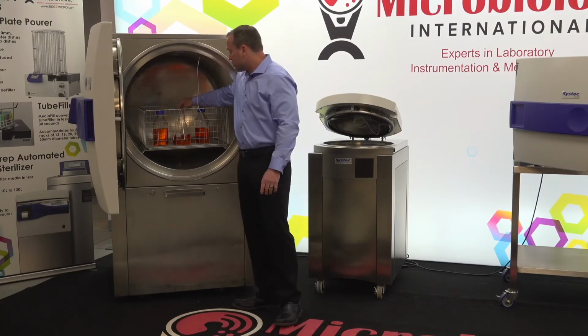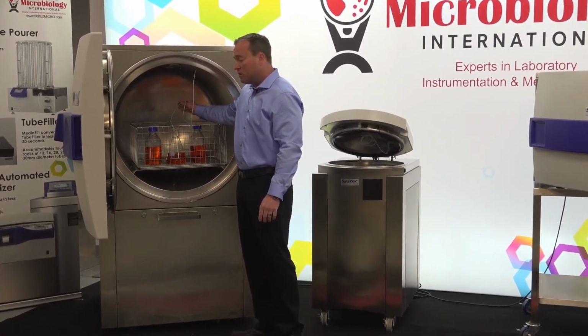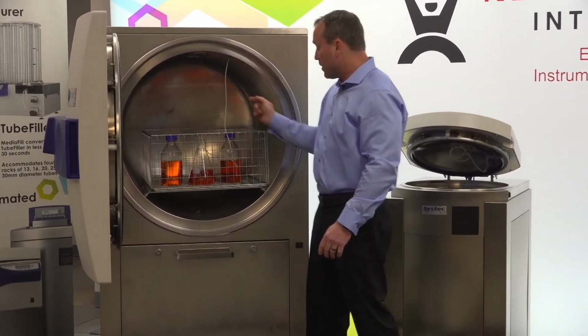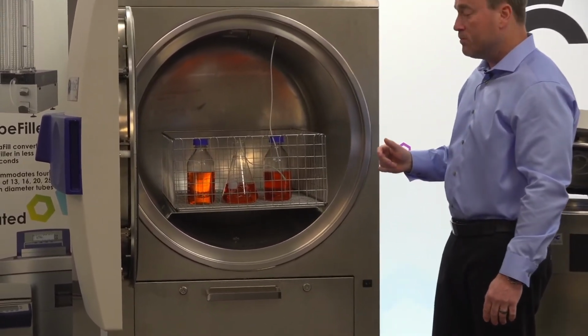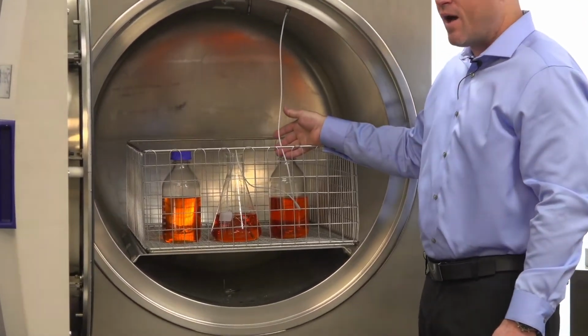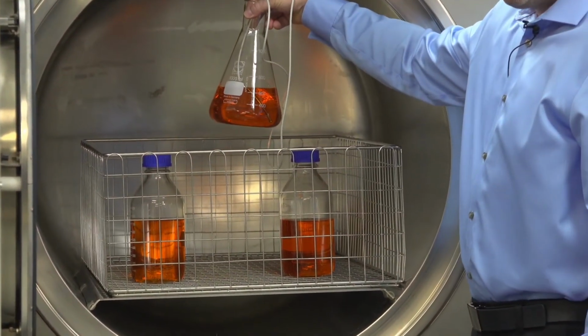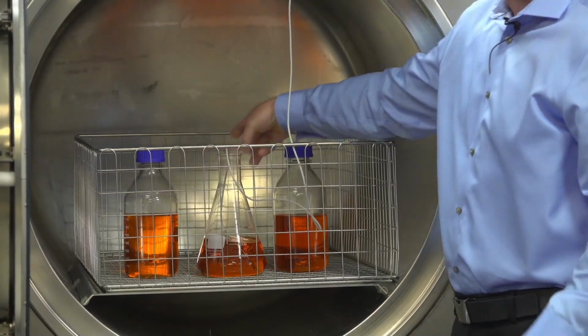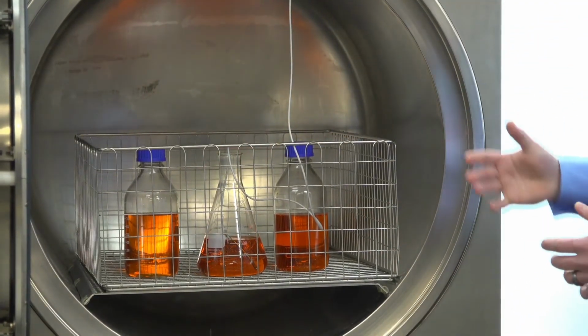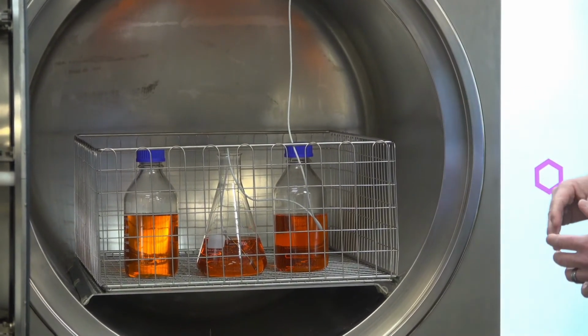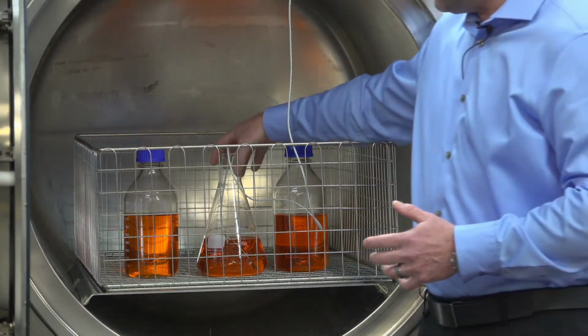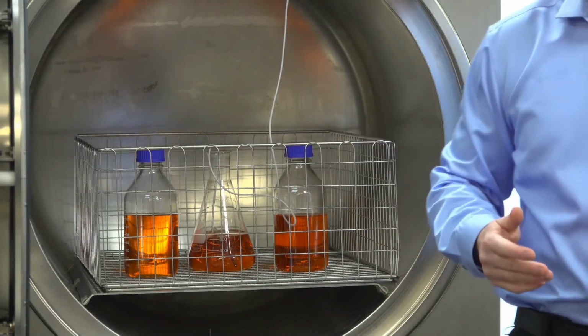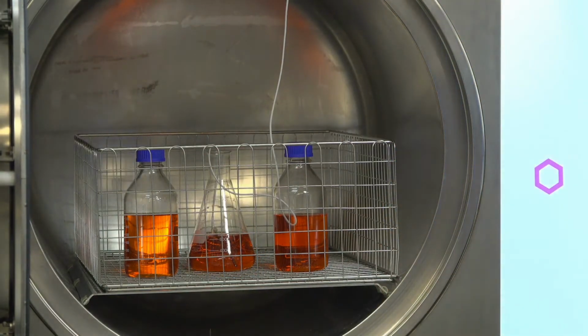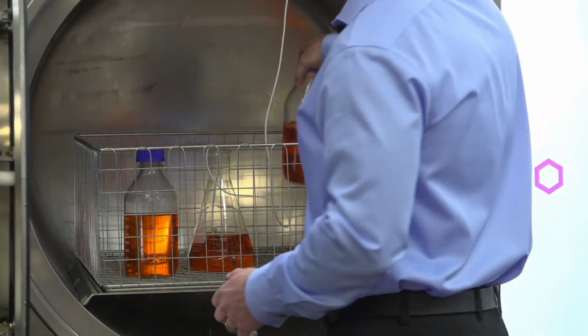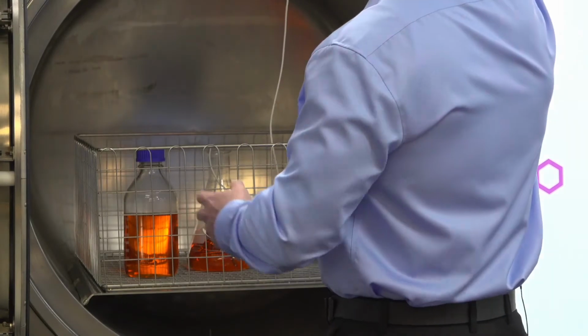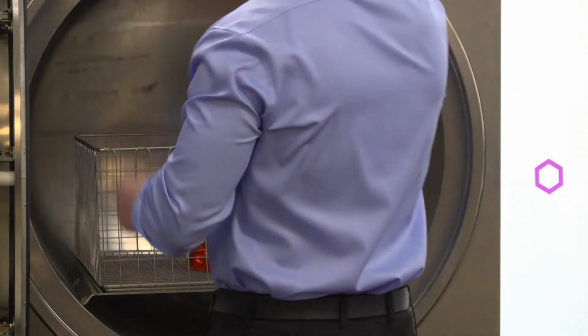So here's our flexible temperature probe in the unit. This is a standard feature. You can zoom into that there. So we can use a reference vessel. So you could either use one of your product vessels that you have, which I've kind of displayed here, or what you can do is have a reference vessel of water. That would need to be the same volume as whatever the bottle is that you're working with, as well as be roughly in the center of the instrument, because that's the one that is going to heat the slowest and also cool the slowest. So we have multiple, again, we have multiple baskets and different options for these instruments.